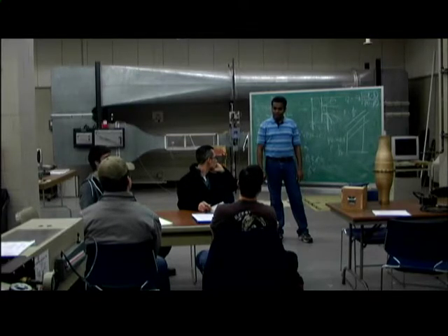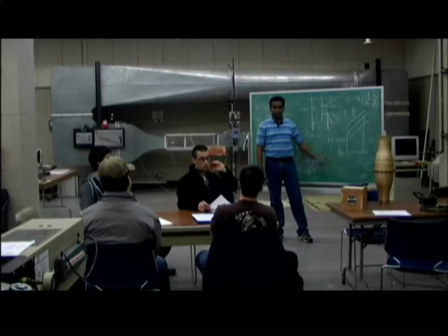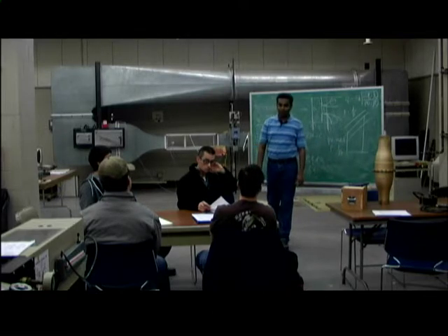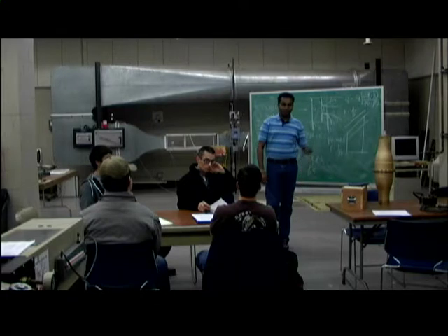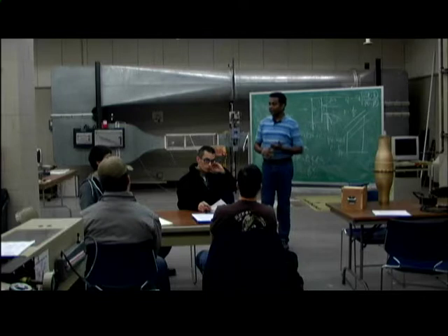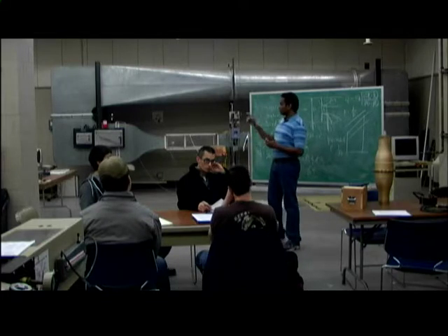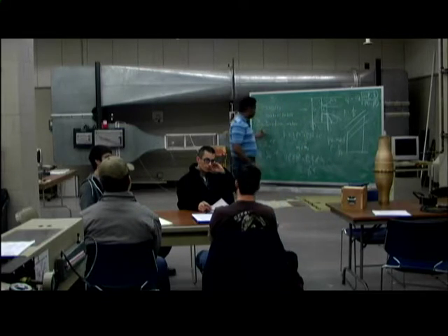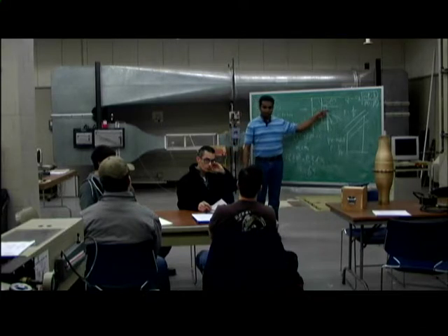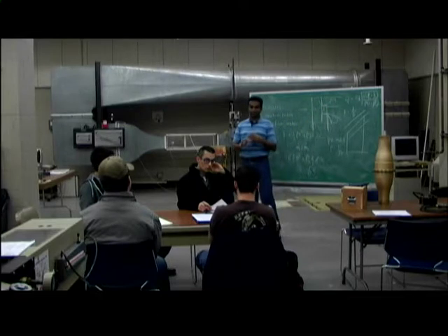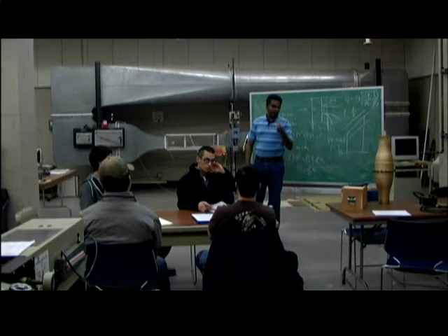Wouldn't that be your barometric, like what we did? Yes. You have to find the absolute pressure. So you have to take the barometer reading as well. Those are the measurements that you can take. You take the pressure difference across the laminar flow element, the pressure difference across the orifice meter, and the pressure difference across the fan, because that pressure is required to calculate rho.